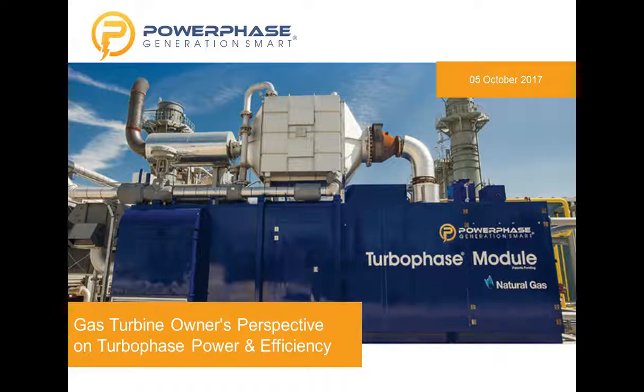Okay, interesting. And do the modules operate only on gas, or are there applications for automotive diesel oil or other types of fuel? Sure. We have essentially the only change in our box is whether I put a gas or a spark ignition engine in them, or I put a liquid fuel or compression ignition engine in them. And we buy those engines, as I mentioned, from MTU or Caterpillar. And so we do offer them in diesel. Our very first unit we built was a diesel unit. So we do both. And so if a customer is running on, I would say everything from LFO to HFO to bunker C or crude, there are engines available to run them. If you can run a genset on that fuel, we can run Turbophase on that fuel.